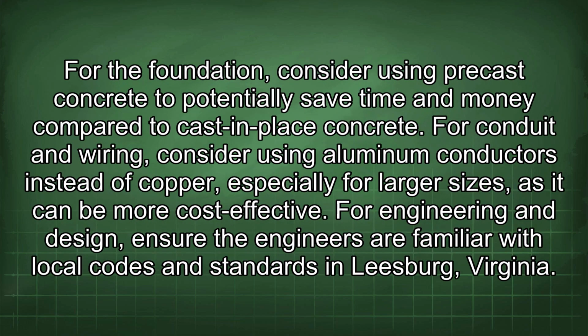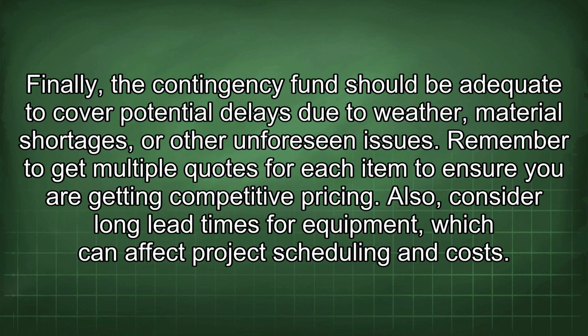For the foundation, consider using precast concrete to potentially save time and money compared to cast-in-place concrete. For conduit and wiring, consider using aluminum conductors instead of copper, especially for larger sizes, as it can be more cost-effective. For engineering and design, ensure the engineers are familiar with local codes and standards in Leesburg, Virginia. Finally, the contingency fund should be adequate to cover potential delays due to weather, material shortages, or other unforeseen issues.